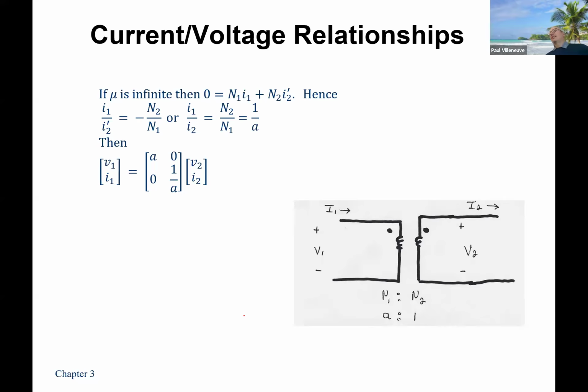The same. Yeah, if the voltage goes up, the current has to go down by the same amount for the power to be the same, right? If I'm plugging in 10 megawatts here and I'm stepping the voltage up by a factor of 10, that current better go down by that same factor to make sure that I get around 10 megawatts coming out. And in an ideal transformer, it'd be exactly 10 megawatts. So they have to be the inverse of each other to maintain that constant power.